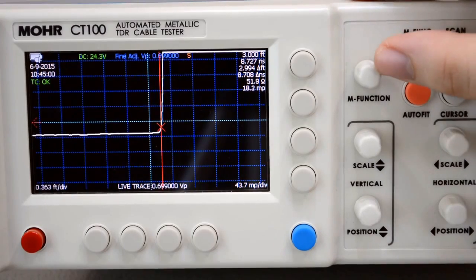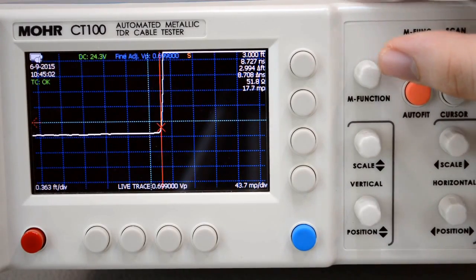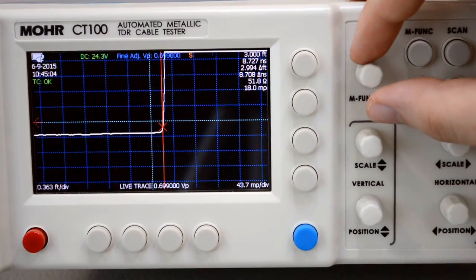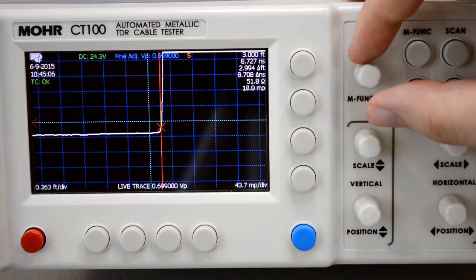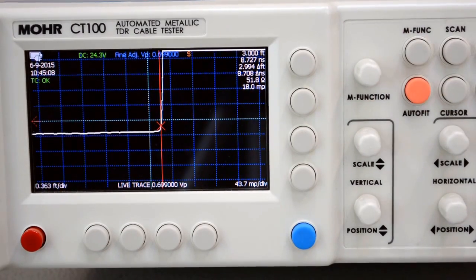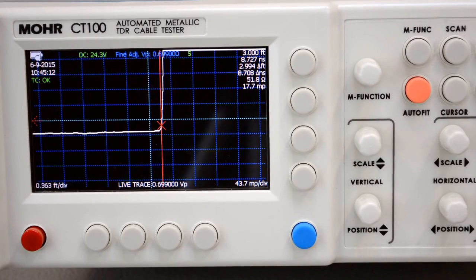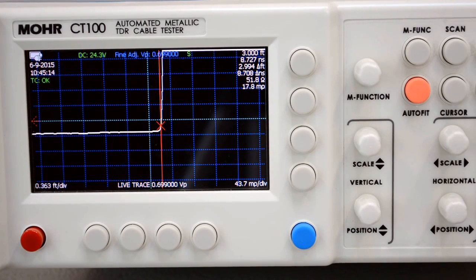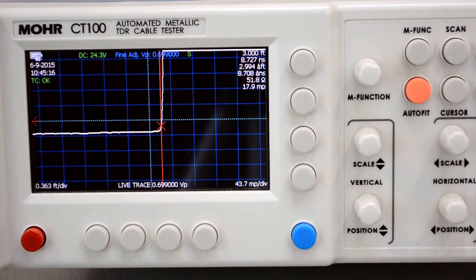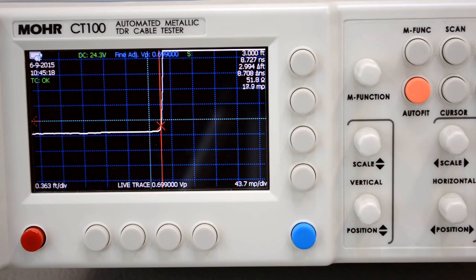Looks like our V sub P is 0.699 which is really close to our expected value of 0.7. Now once you found the V sub P you can use that V sub P on all other cables from this length of cable and you'll be able to get an accurate reading, an accurate measurement from all of them.